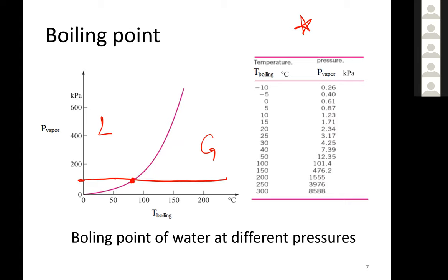And this is basically the point upon which the principle of air conditioning revolves. What I need to do is allow phase change at almost atmospheric condition. What happens in that case? The temperature has to drop down to the boiling point at the evaporator pressure. And this has more to do with the selection of the refrigerant. When I select a refrigerant, I need to check this curve. The curve I am showing here is for water, but we have similar curves for refrigerants. I need to make sure that the refrigerant will have the desired boiling point at the evaporator pressure. And again, at the condenser pressure, I need a boiling point that is suitable enough to allow transfer of heat from the condenser to the outside.